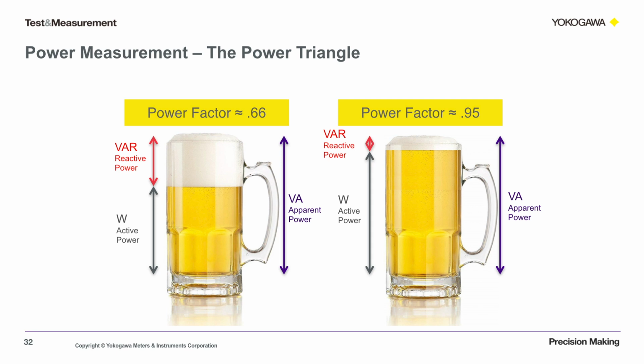The beer that's doing the work is the active power. That's the beer quenching your thirst. The reactive power is not doing anything other than giving you a mustache when you're drinking. You would much rather have a beer closer to the right, which is closer to a unity power factor. Putting this into electrical terms, if you had an electrical system with a power factor similar to the one on the left, the conductors would need to be sized to carry the voltage and current calculated by the apparent power, but you're only using the active portion of it. So you must account for the reactive wasted power. With a larger conductor comes more cost, weight, and losses.